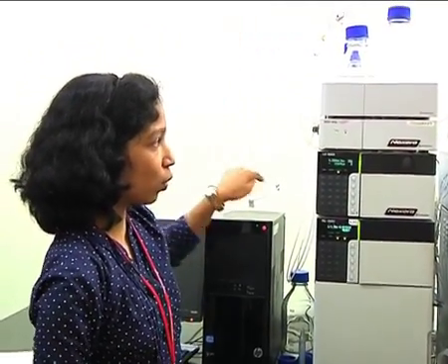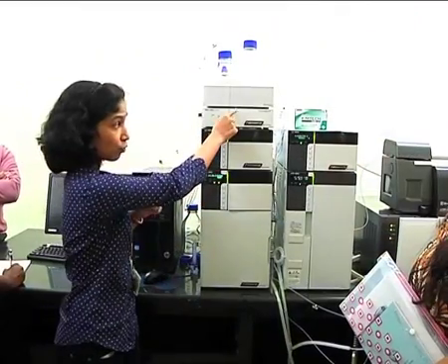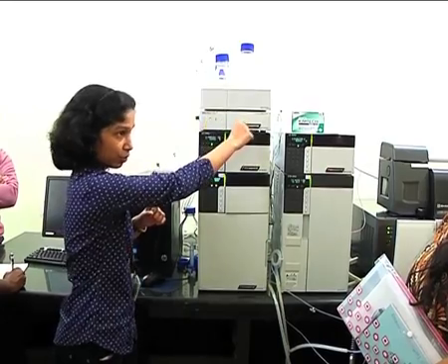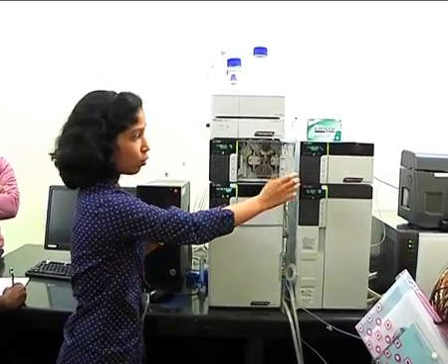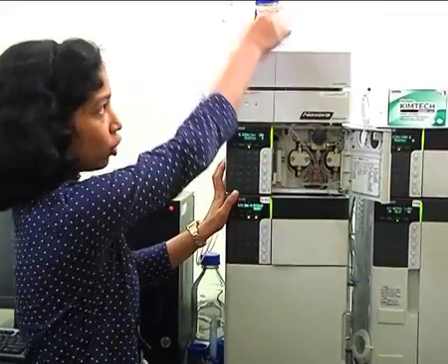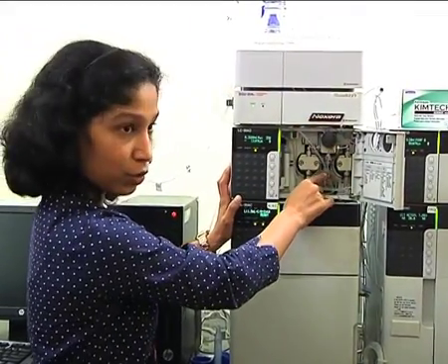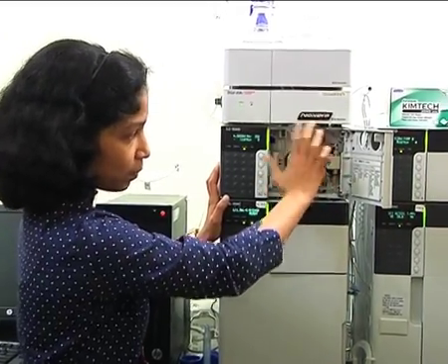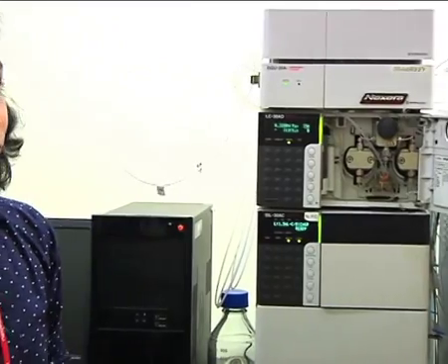The other model is low pressure quaternary, where there is only one pumping unit and four reservoirs, and one pump controls all four. These two are the pumping units. From the mobile phase, it goes first to the degasser unit. From the degasser unit, the mobile phase comes to the respective pumping system. Suppose this is pump A; from the degasser unit it comes to this. This pumping unit is a dual plunger reciprocating type of pump.